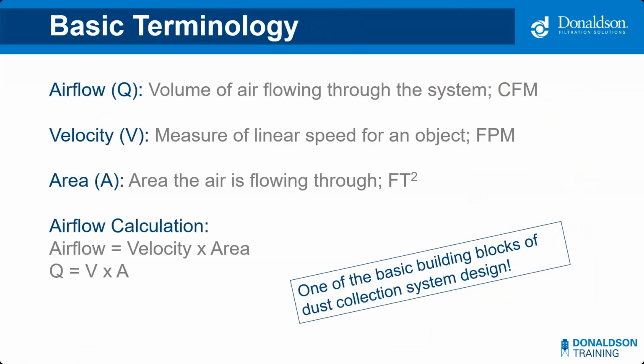Okay. There are many different terminologies and formulas we use in dust collection system design. The most basic and widely applied being airflow. The formula is Q equals V times A. Q is the volume of air flowing through the system, often referred to as CFM, cubic feet per minute. To get the airflow, we multiply the velocity of air, which is the measure of linear speed of it for an object, by the area of the hood or duct that the air is flowing through. The formula is one of the basic building blocks of dust collection system design.